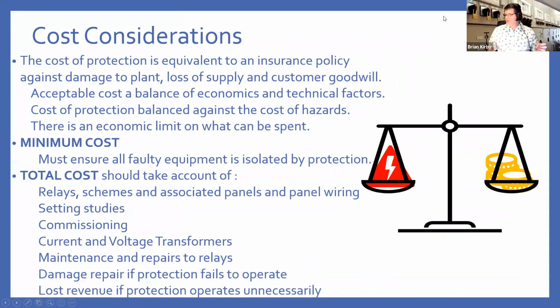However, as we know, insurance is a financial balance. You've got to look at the cost of protection against the cost of the loss of supply and the damage to equipment. So if you have a small transformer that's going to cost you £20,000 to replace, you're not going to spend £40,000 on protection for that. But if you have a high voltage transmission transformer costing hundreds of thousands of pounds, then £25,000, £30,000 on protection schemes is a good investment at that point. So it's always a cost balance.